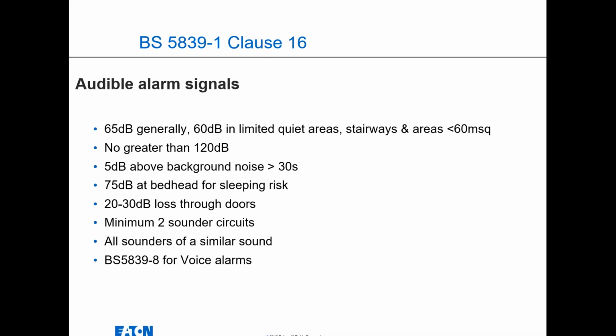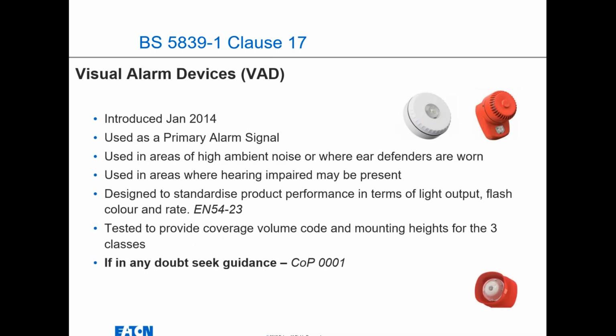And especially in a bedroom where you need to achieve 75 at the bed head, you almost have to have a sounder within the vicinity of that room. So in most hotels, they generally have a smoke detector with a sounder base, and sometimes obviously nowadays a visual alarm device, which brings me nicely into visual alarm devices.